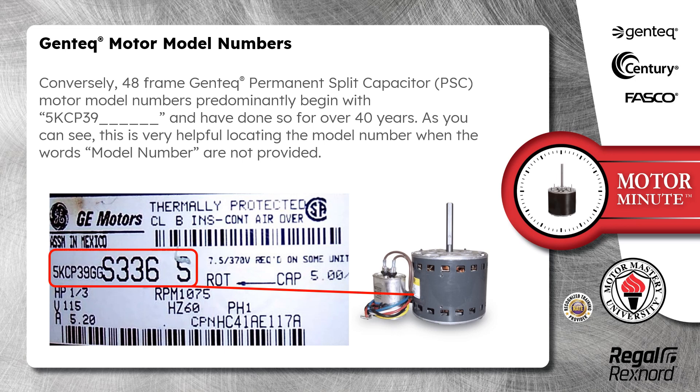Conversely, 48-frame Genteq permanent split capacitor PSC motor model numbers predominantly begin with 5KCP39HX and have done so for over 40 years. As you can see, this is very helpful in locating the model number when the words "model number" are not provided.